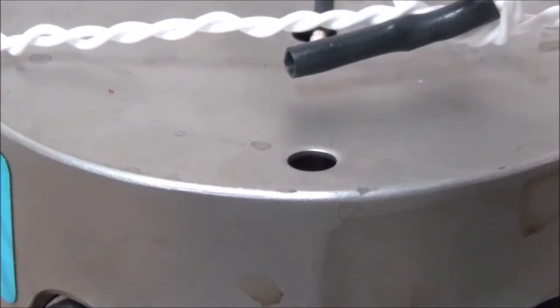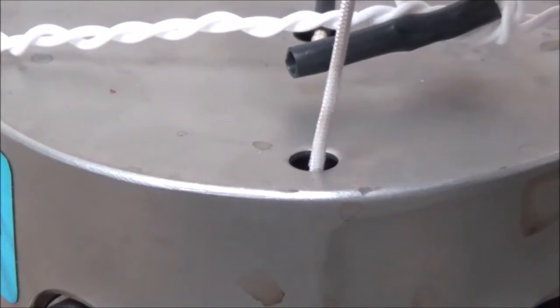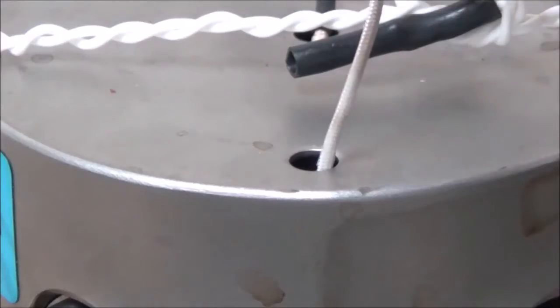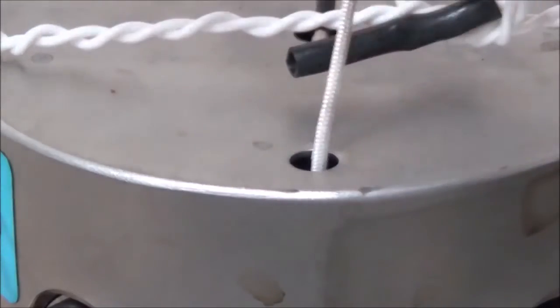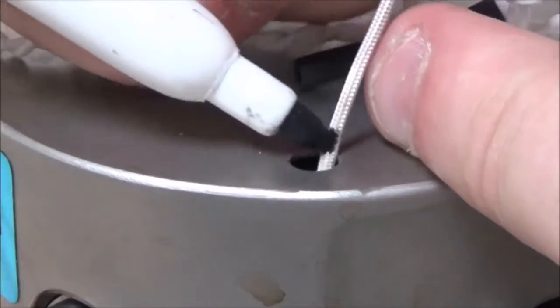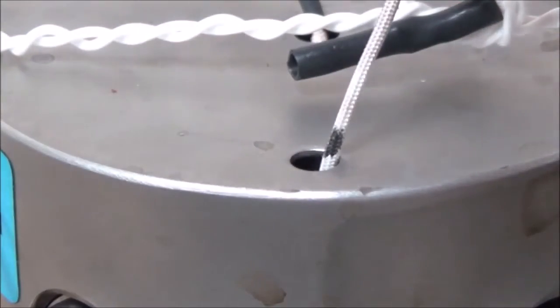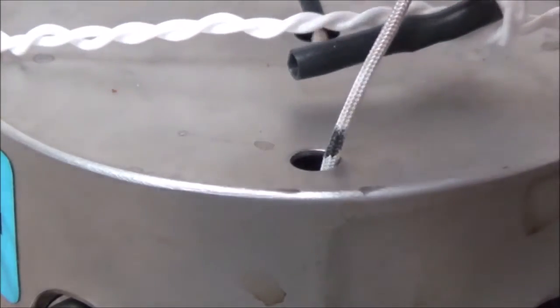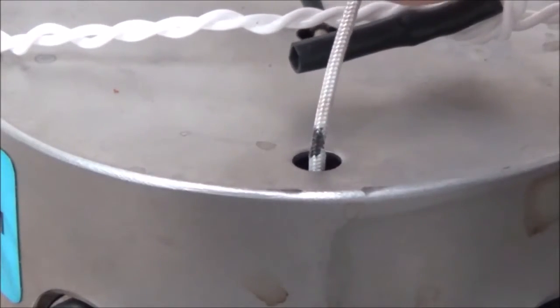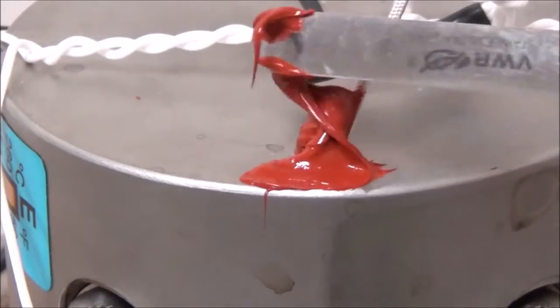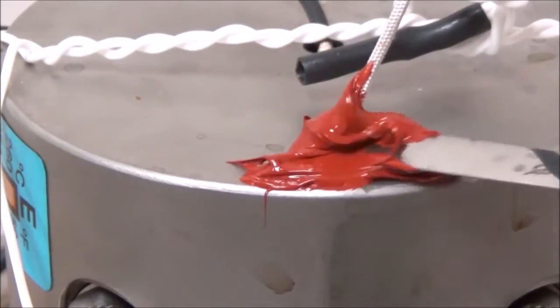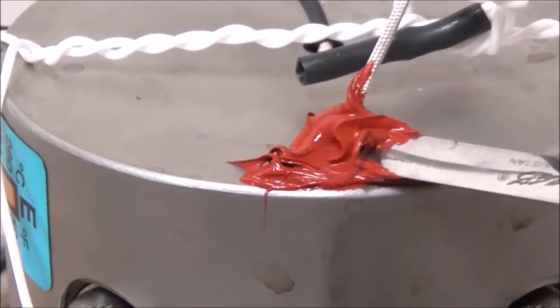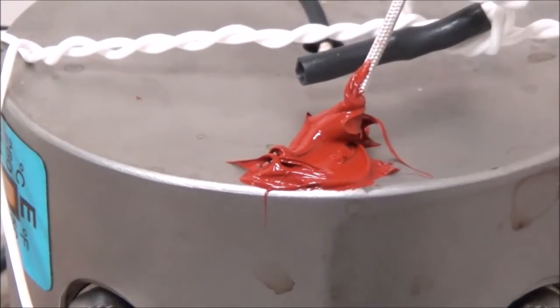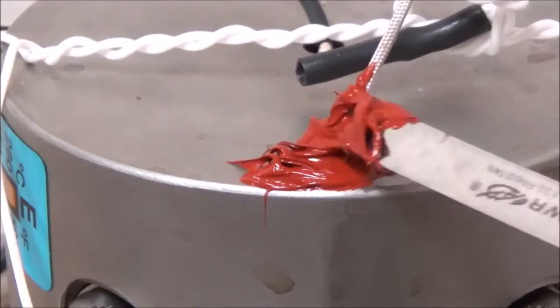When you have located the block RTD hole, gently slide in the RTD itself until met with resistance. Then, using a permanent marker or pencil, mark off where the RTD stops. This step is crucial in determining whether the RTD has been accurately placed. Once the RTD has been correctly placed, add adhesive or glue to the RTD hole to prevent the RTD from sliding out of place during reassembly.